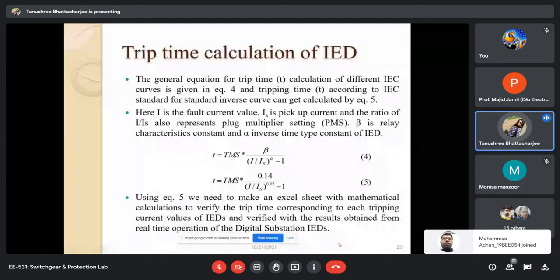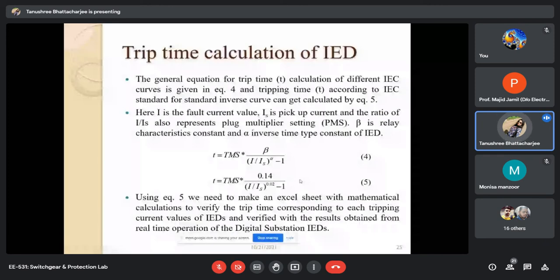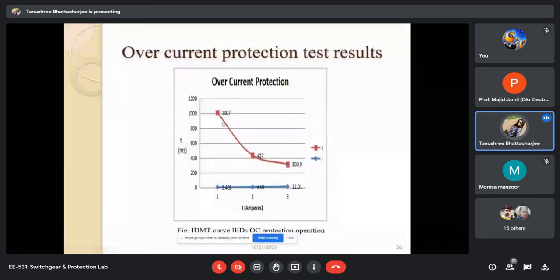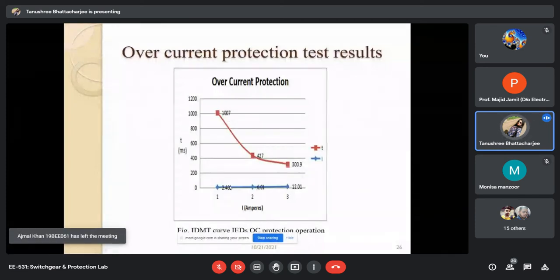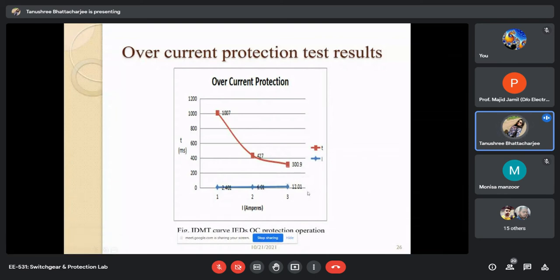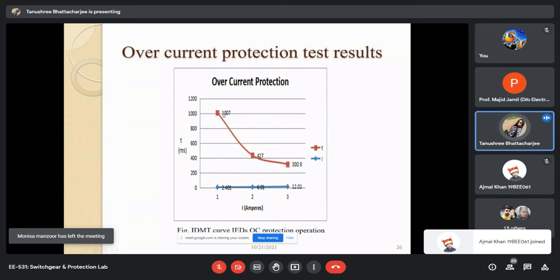Okay, so these are the time calculation equations which I have explained. Now this is the protection curve, the IDMT curve we have got with this overcurrent protection. We have taken three values of increasing current, multiplied by 2, by 5 and by 10 of the trip value. And the tripping value we have taken is 120% of our normal current, which is 1.2 kiloampere. And these are the respective time values corresponding to the current.